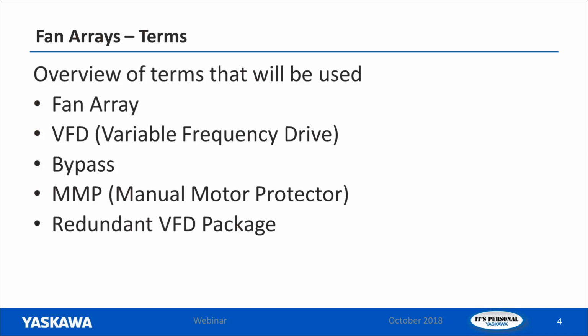And then redundant VFD package. This is going to be very similar to bypass. So if you imagine a VFD with bypass, the redundant VFD package would just have another VFD in that bypass section. So you're really just bouncing back and forth between VFDs if you're going to switch in and out of bypass.